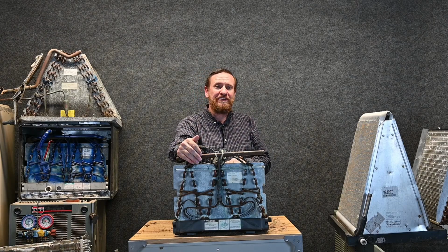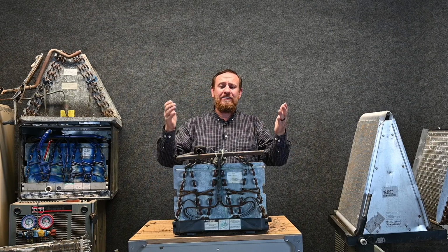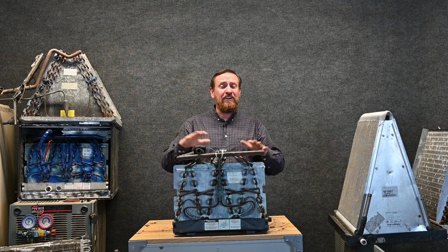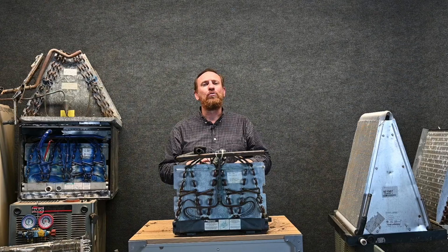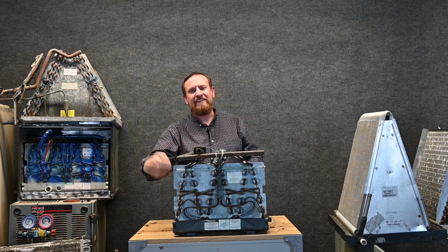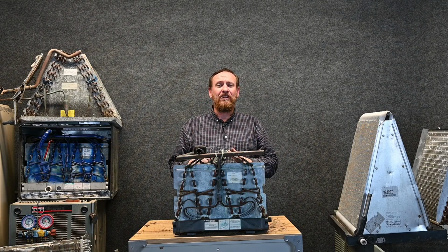And we're going to have to pressure test the lines, and we're going to have to pull it down below 500 microns and let it hold for 30 minutes. So it's very expensive doing an evaporator coil clean. A lot of companies, instead of calling it a coil clean, call it a coil recondition. And I'm really on board with that, because it's not like we're just cleaning this thing up, oh, just make it shiny. We're literally having to pull it out and recondition it. It's a lot of work to do that.